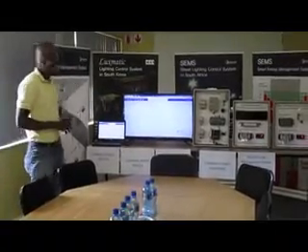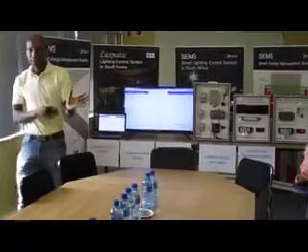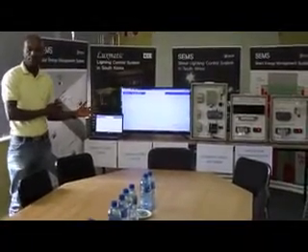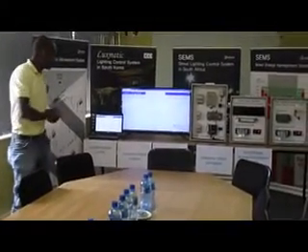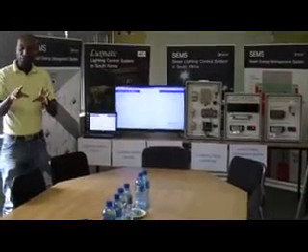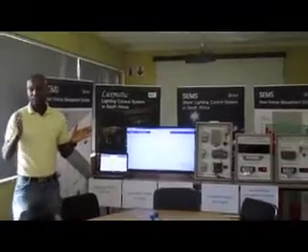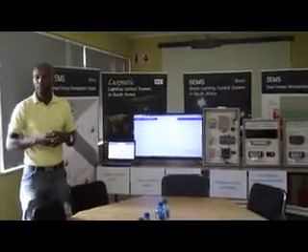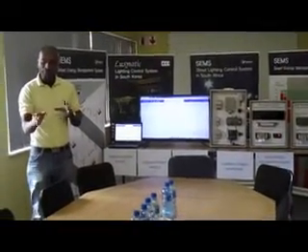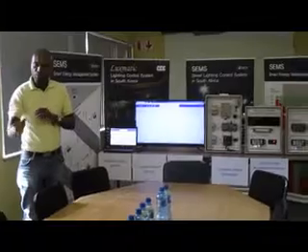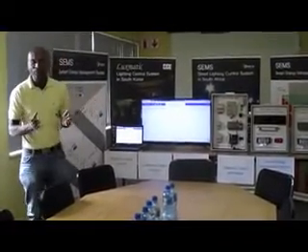Now, with what we're implementing here in Bloemfontein, our system has two parts. The first part is software, and the other part is hardware. With the software, we are able to set the system according to the client's needs. When it's sunset, it goes on at 100%, and then maybe around 1 hour after that, it can go to 80%. Around 12 in the morning, it dims automatically to 50%. With that, we can see it's going to save a lot of power.